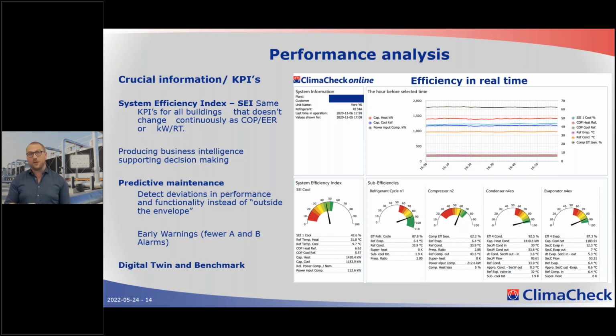This gives you a map directly to whether it's performing well for your system, and it even takes account of ambient temperature, so you don't need to do other calculations. If you know that your system is supposed to have a system efficiency index of 43.6%, which is here, and that's good, then you know it's fine.